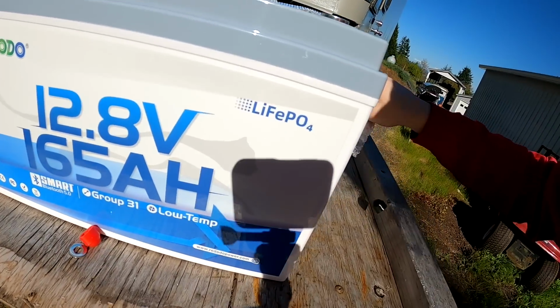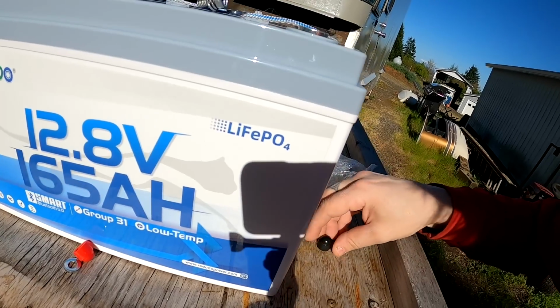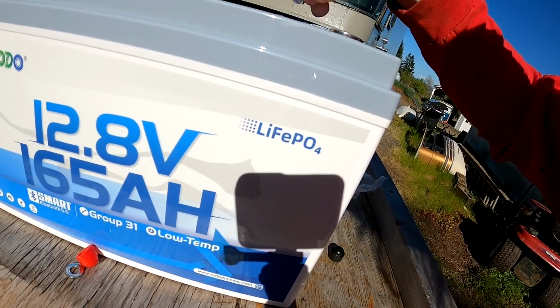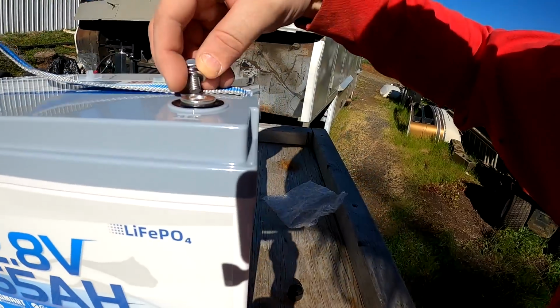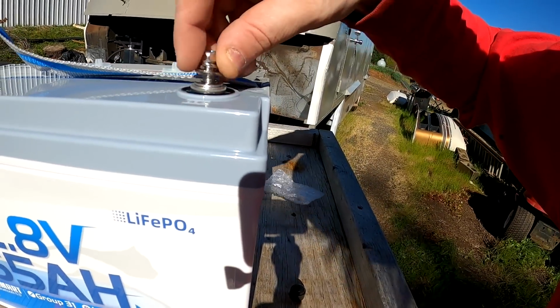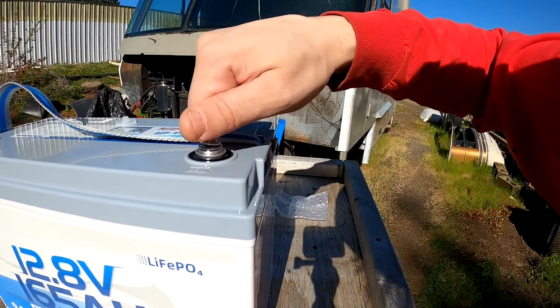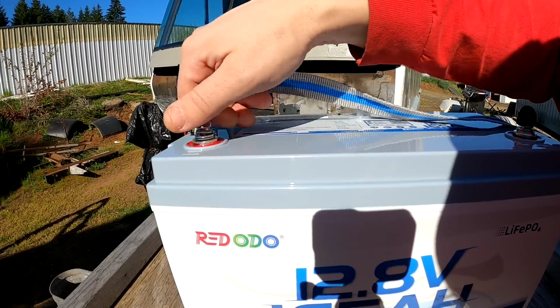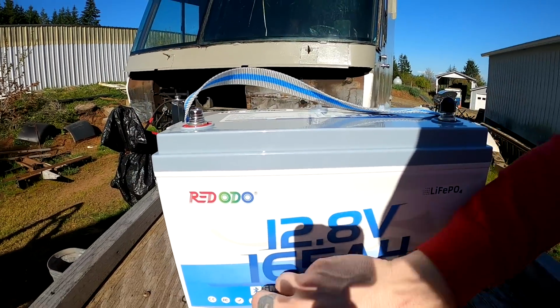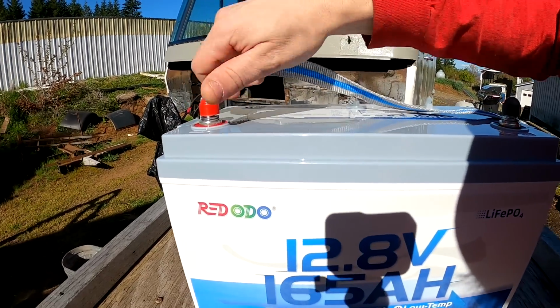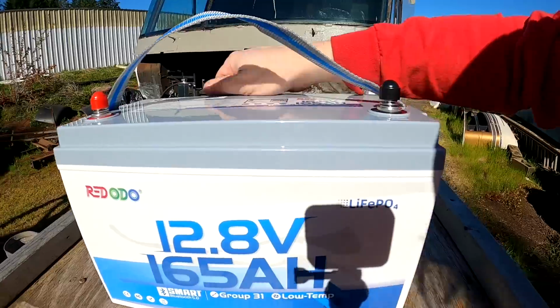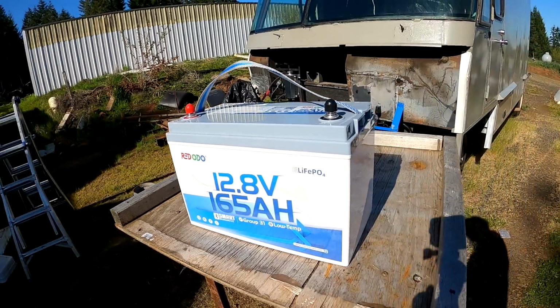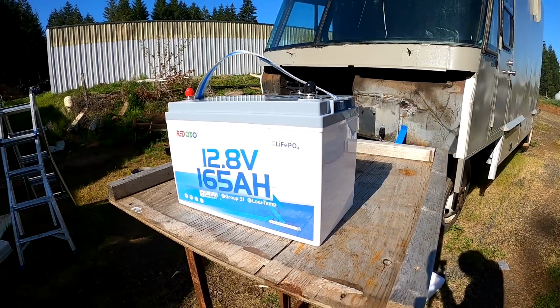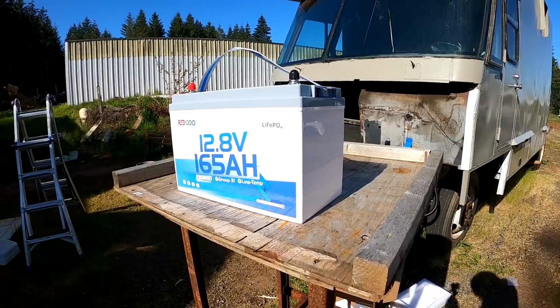Market leading high power 165 amp BMS with max continuous output power of 2,112 watts easily powers high demand devices. Plus, it can handle surge currents of 825 amps for 1 second and a surge of 495 amps at 5 seconds. Reinforced with a metal plate structure to enhance heat dissipation and cell fixation capabilities, extend battery life, and ensure safety.